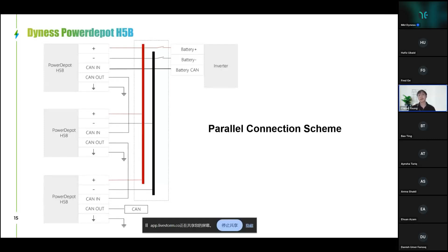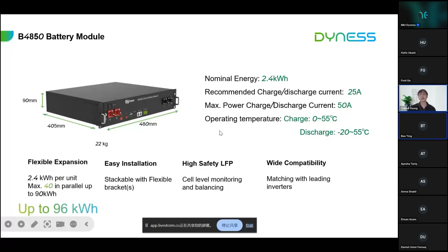This one is our most widely spread product with the very best long-term financial efficiency, containing a series of 50 ampere hour battery cells at 48 volts. Every battery module has a capacity of 2.4 kilowatt hours, supporting maximum 1C charge and discharge. It also supports large-scale parallel connection up to 40 pieces, which is 96 kilowatt hours.